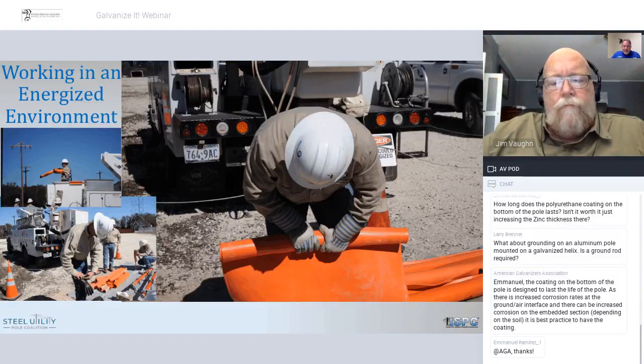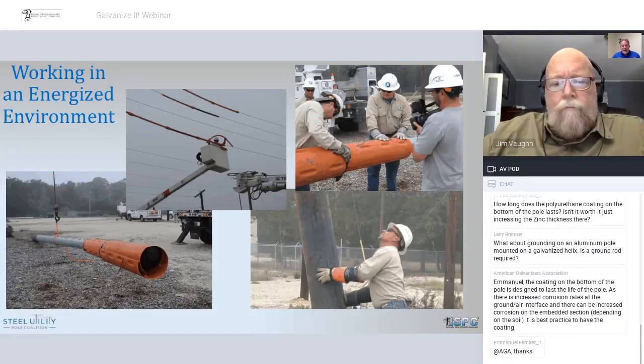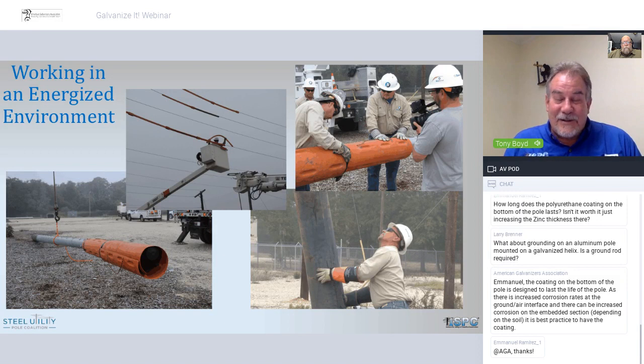Hey, Jim. Working the energized environment, like we've said many times already, it's just like working with the wood poles. There's a few differences. We know that the steel is a better conductor than the wood. The steel is lighter than the wood, so it makes it easier to handle. Someone wearing rubber gloves at the bottom of the pole would be less likely to have to hug the pole to maintain control, to get it into the claws of a digger derrick. Where a wooden pole being so heavy, I've seen guys just grab the pole and hug it. So what is your rubber gloves doing? So being lighter makes it easier to maneuver.